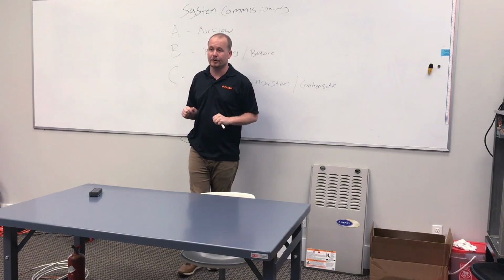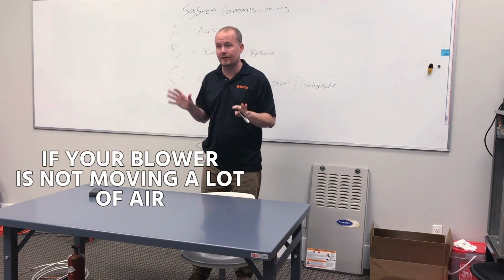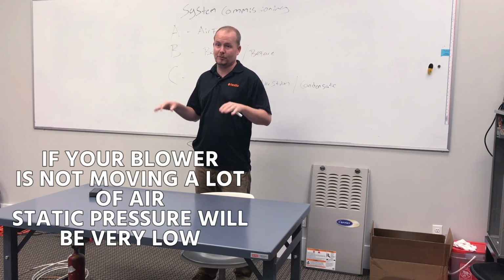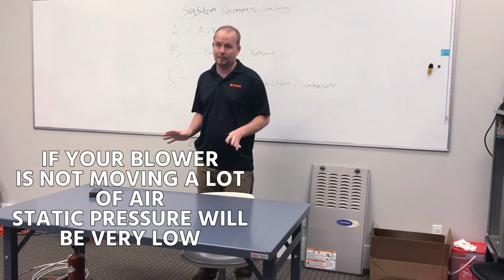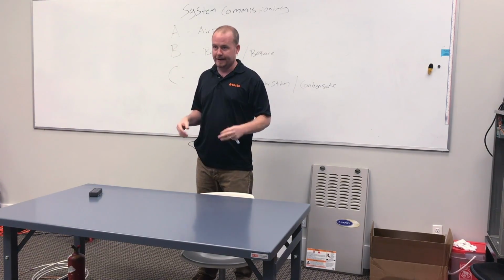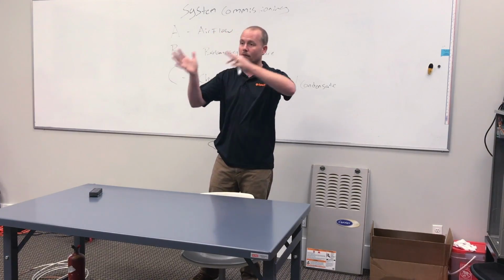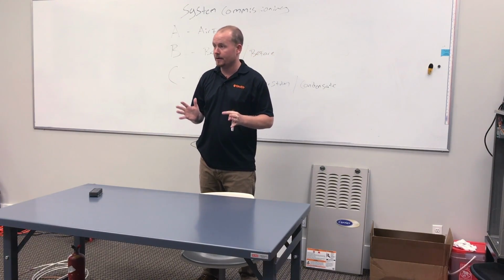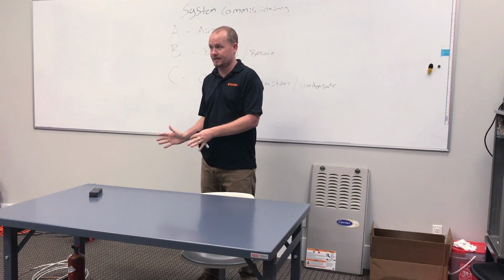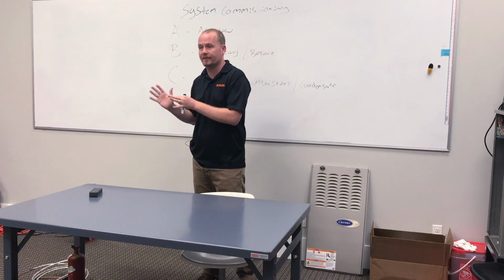It's the same thing with your duct system. If your blower is not moving a lot of air, your static pressure will be very low. Static pressure is like blood pressure, right? You get the correlation here? And so you've got to have that blower running up to the speed it's supposed to run before your static pressure can be trusted, because static pressure is not a measurement of airflow.